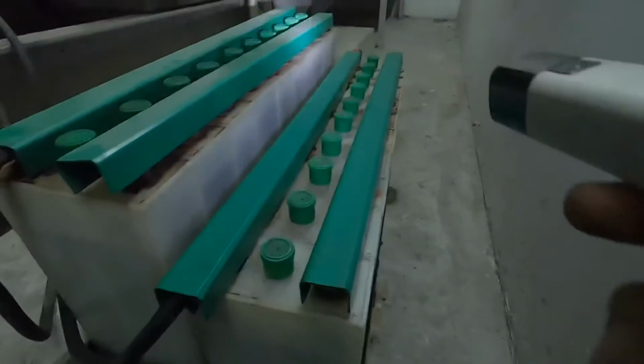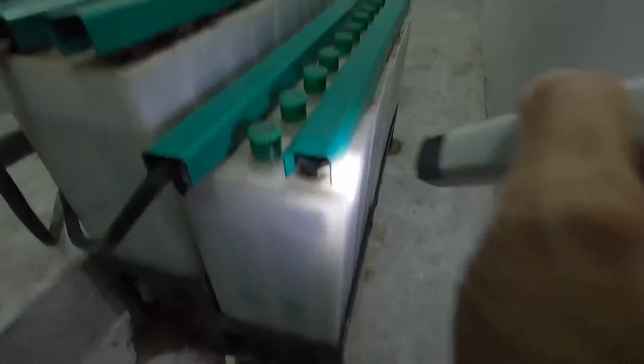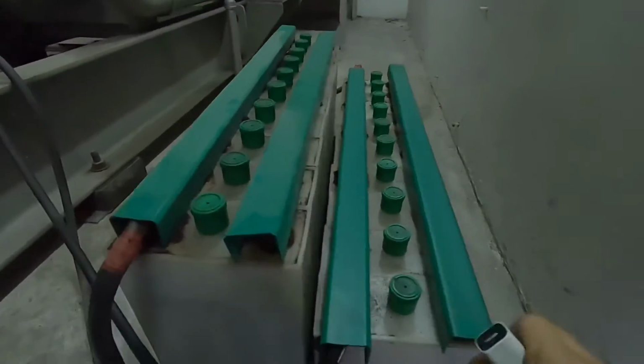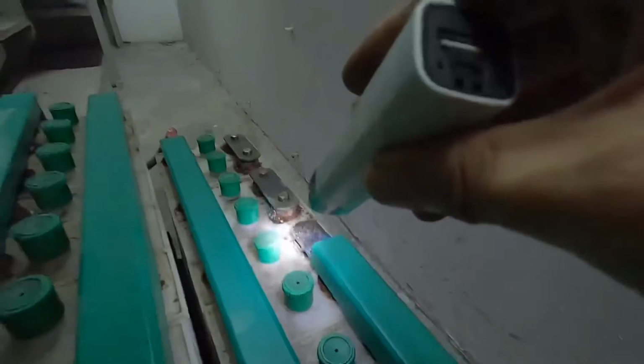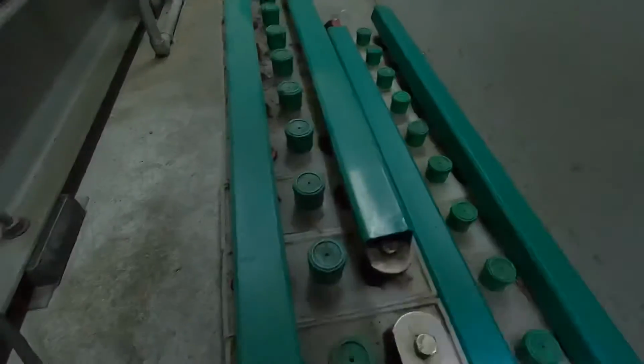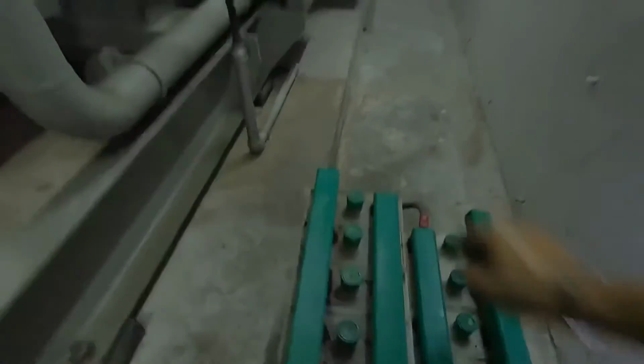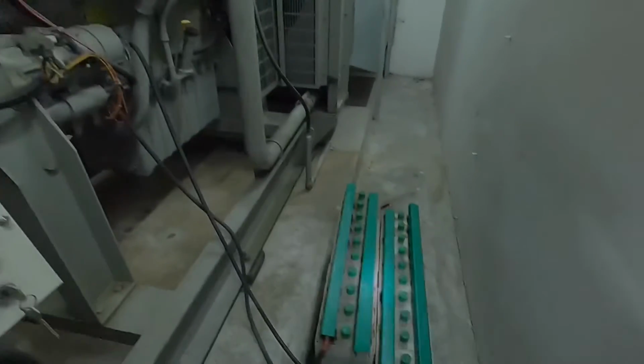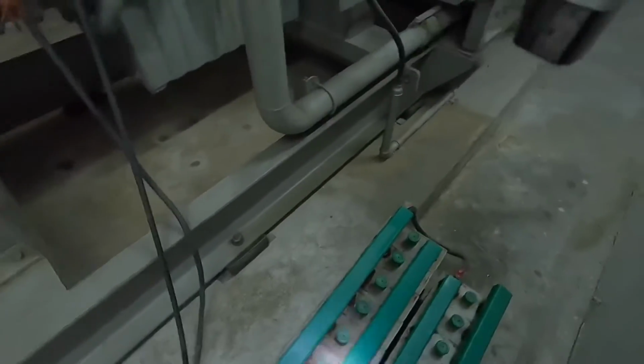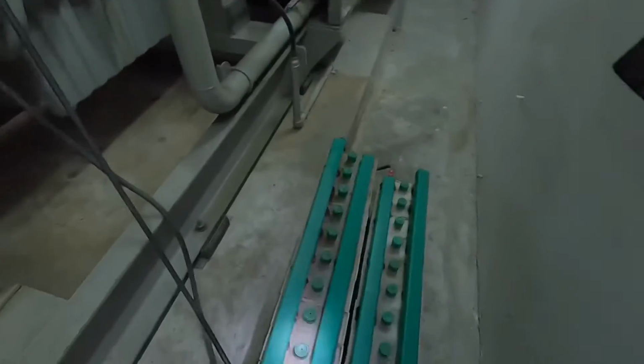So let's just check this side, the battery. Okay, make sure battery water level is all full, good condition. Battery termination, this one requires servicing because some of the termination is quite corroded, rusted and oxidized. Servicing of the battery is required due to previously the termination not having an external film of Vaseline or petroleum jelly or grease to protect it from oxidization. Okay, let's check the terminal, make sure it's tightened. Okay, the cable didn't harden.